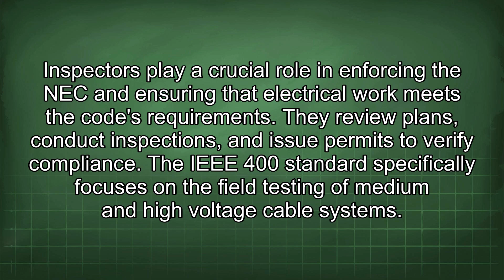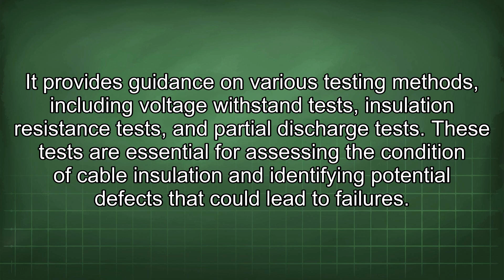The IEEE 400 standard specifically focuses on the field testing of medium and high voltage cable systems. It provides guidance on various testing methods, including voltage withstand tests, insulation resistance tests, and partial discharge tests. These tests are essential for assessing the condition of cable insulation and identifying potential defects that could lead to failures. The IEEE 400 standard also covers the interpretation of test results and the development of maintenance strategies based on the findings. It helps to ensure the long-term reliability and performance of medium and high voltage cable systems.